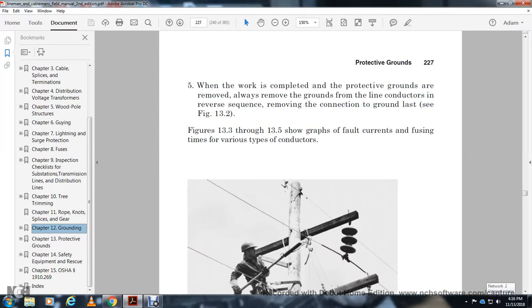5. When work is complete and the protective grounds are removed, always remove the ground from the line conductors in reverse sequence. Remove the connection to the ground last. Figures 13.3 through 13.5 show graphs of fault currents and fusing times for various types of conductors.